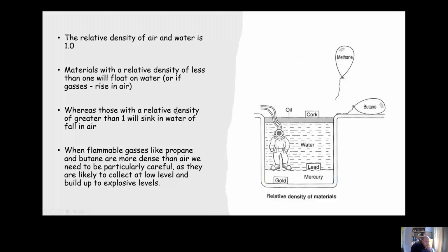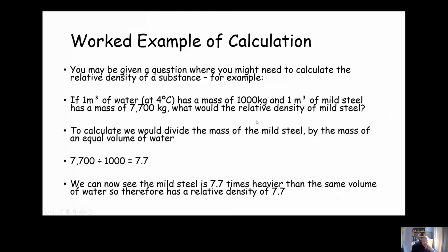Alrighty. One thing worth noting: propane and butane, as we've said before, are both more dense than air, both heavier than air. So you need to be very careful if you work with them, particularly in excavations, because they're heavier than air, they'll fall down and they can collect at ground level and could build up to explosive levels. So just be very careful.